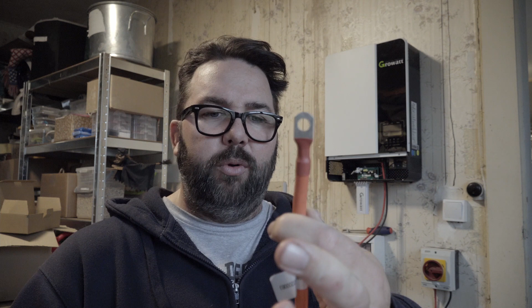Now I've seen on the internet a lot of people put fuses and breakers between the battery and the inverter. I've been in contact with the company I ordered all this stuff from, and they said no, just batteries straight to the inverter, no fuses or breakers needed. We don't need any breakers because I can disconnect the batteries - they've got a power switch on the front, and they say they don't need to be fused.